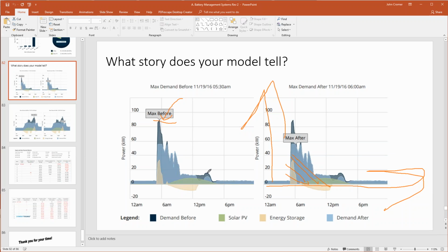And it used to be that solar was not very good for demand charges, but now it's the best market. Because solar would only occur during the day, and if that didn't coincide with your period of maximum demand, then solar doesn't do anything for your demand charges. And even when solar coincides with your period of demand, on a partly cloudy day, your demand is where it normally is, your solar array is jumping up and down because of the clouds, you might not get any demand savings because your peak is still as before.